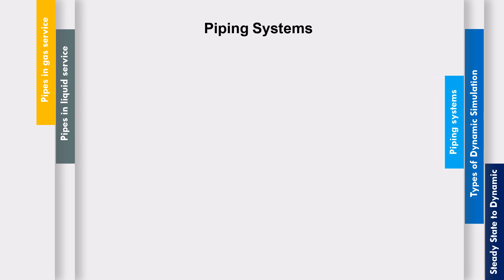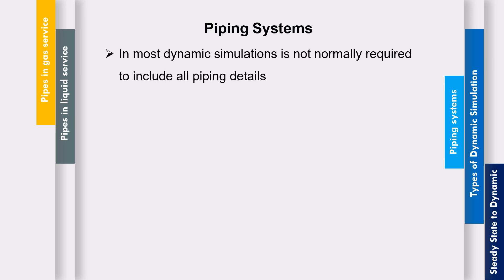Now, regarding piping systems: in most dynamic simulations, we do not include all the piping details because the liquid holdups or volume holdups in pipes are very small compared to other equipment. For example, the volume holdup in a distillation column is much higher than in the pipes, so we typically don't consider pipe details. However, if the pipe is extremely large, there is a significant holdup in it and the volume in the pipe is no longer negligible. In that case, we have to include the sizing and pipe details to calculate accurate results.